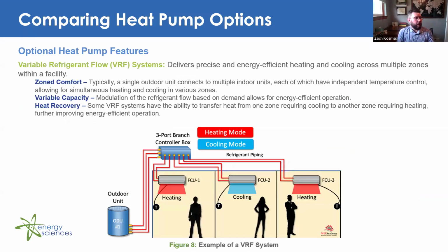So we also need to compare heat pump options. So I'm just going to run through some heat pump options and provide some examples where these specific options may be useful. So the first is a very interesting one. It is called variable refrigerant flow systems, or VRF systems. So these deliver precise and energy efficient heating and cooling across multiple zones within a facility. So for example, if you have a traditional big rooftop unit that's serving multiple zones, and that's reaching the end of its lifespan, a VRF packaged rooftop heat pump system may be a good replacement for that case.